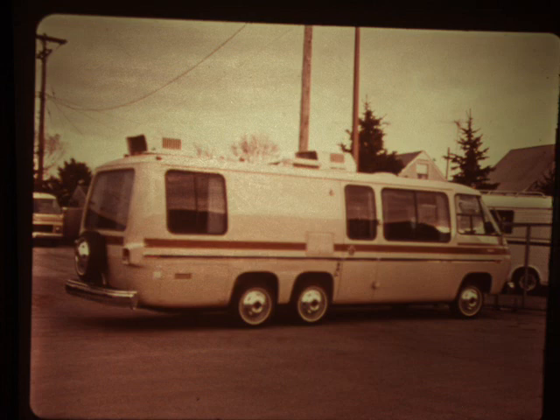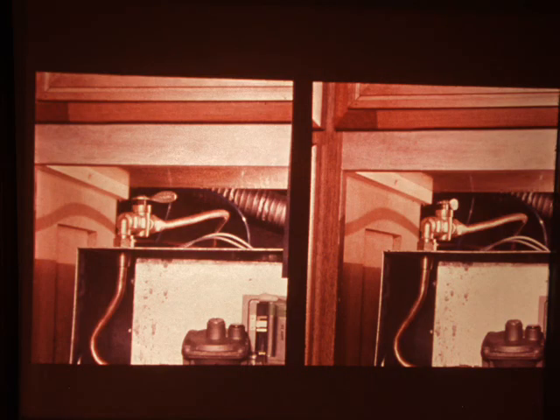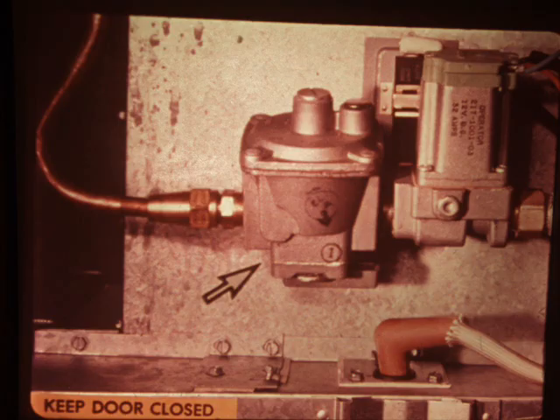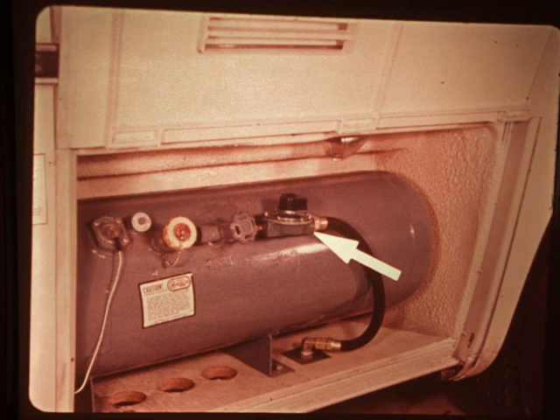Now let's look at the main components of the furnace and how the system works. There's a manual gas valve on top of the furnace. It must be fully open for the furnace to operate properly. The gas control valve on the front of the furnace is a combination manual shutoff and pressure regulator. A pressure regulator on the furnace is a federal requirement. This is in addition to the gas pressure regulator valve on the LP supply tank.